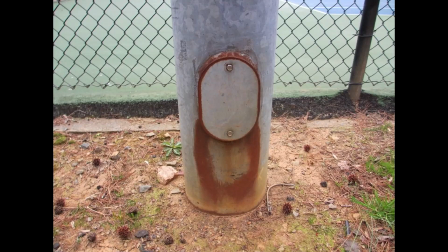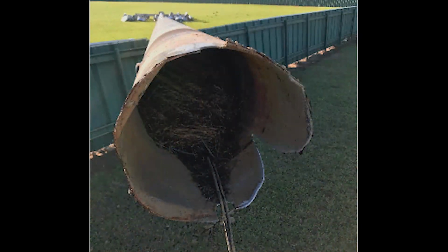Conducting a visual and thorough inspection of your poles every year is a good way to stay ahead of any problems that may occur. And if you see any red flags in terms of corrosion, fatigue, or other areas, you should call in a professional inspection company to conduct more extensive testing and resolve any problems. However, there are structural integrity issues such as weld fatigue, galvanized thickness, and corrosion on the interior of the pole that may not be visible during a visual inspection. Most corrosion occurs from the inside out, so if you're seeing even a little corrosion, rust, or fatigue during your visual inspection, it could be the sign of a larger problem happening internally.